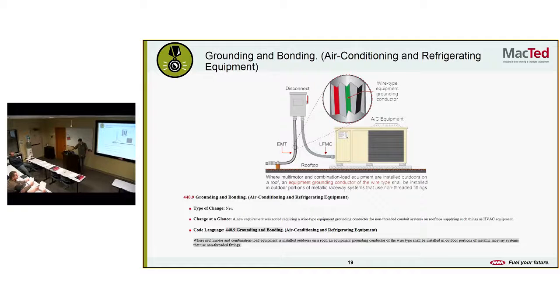Grounding and bonding, air conditioning and refrigeration equipment. This is a new code. A new requirement was added requiring a wire type equipment grounding conductor for non-threaded conduit systems on rooftops supplying such things as HVAC equipment. Where multimotor and combination load equipment is installed outdoors on a roof, an equipment grounding conductor of the wire type shall be installed in outdoor portions of metallic raceway systems that use non-threaded fittings. It's like EMT, is what it sounds like to me. EMT has a tendency to pull apart because it's just that set screw. And if you're using that as the grounding means, you can pull apart, now you don't have a ground anymore. So they've said if it's non-threaded, you need to run a grounding conductor in there now.